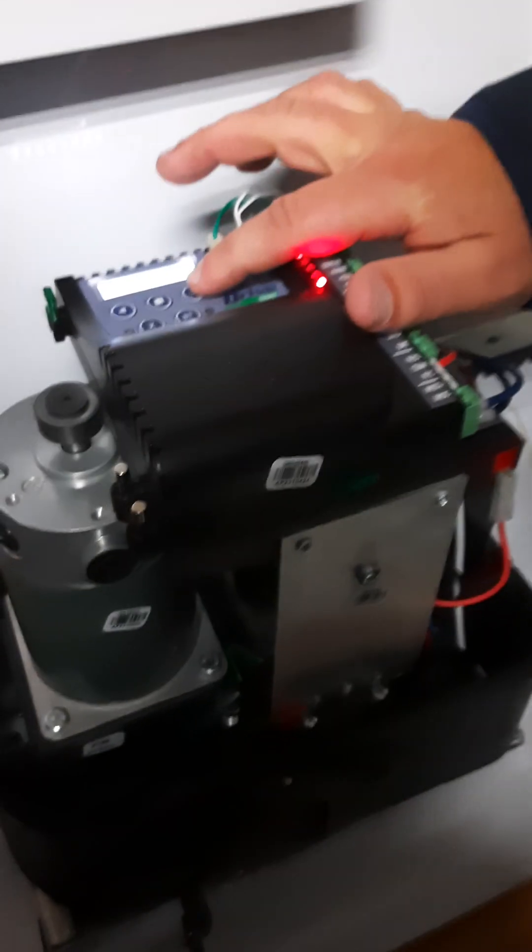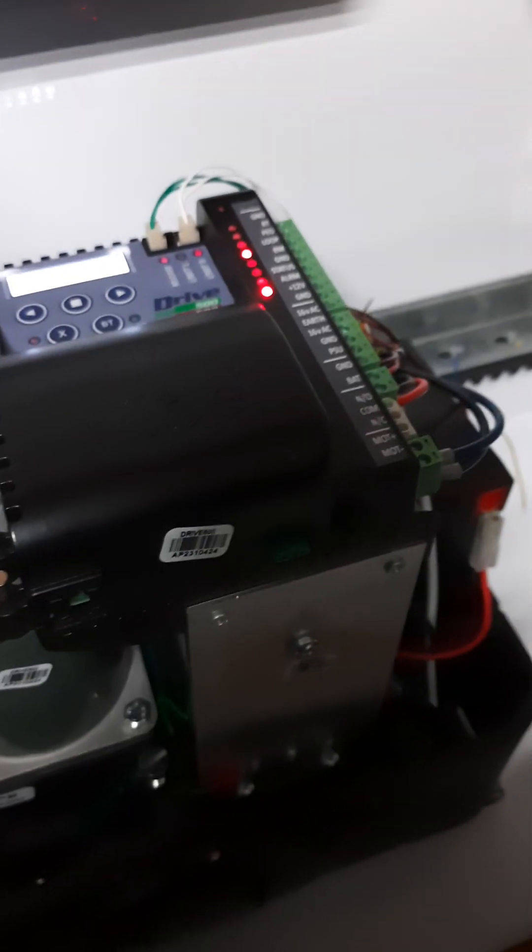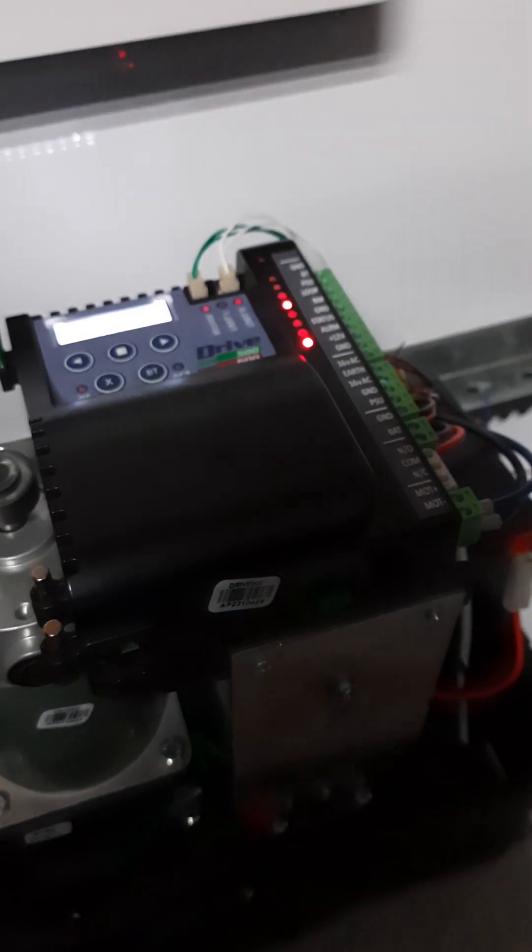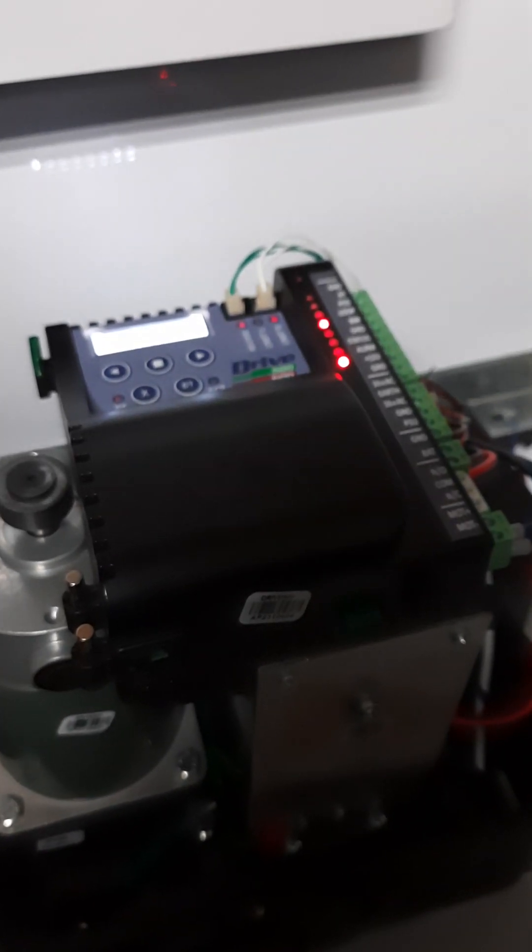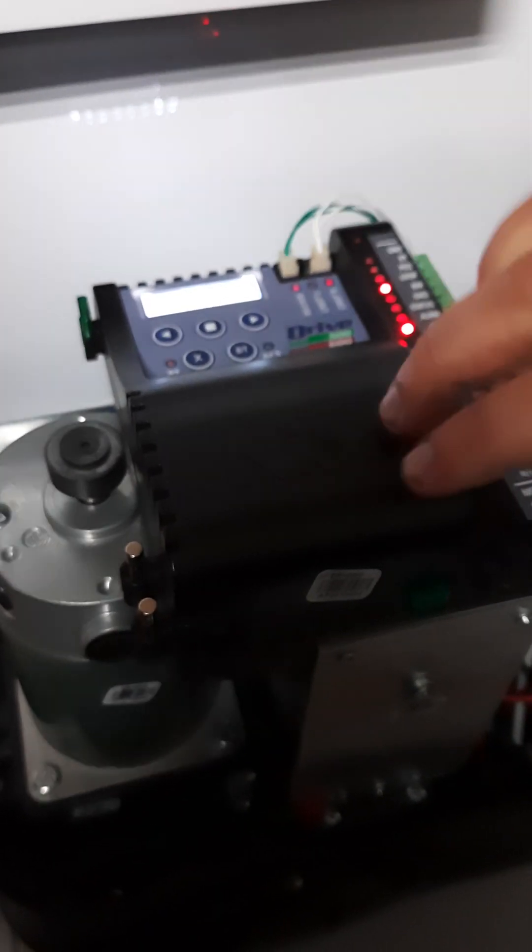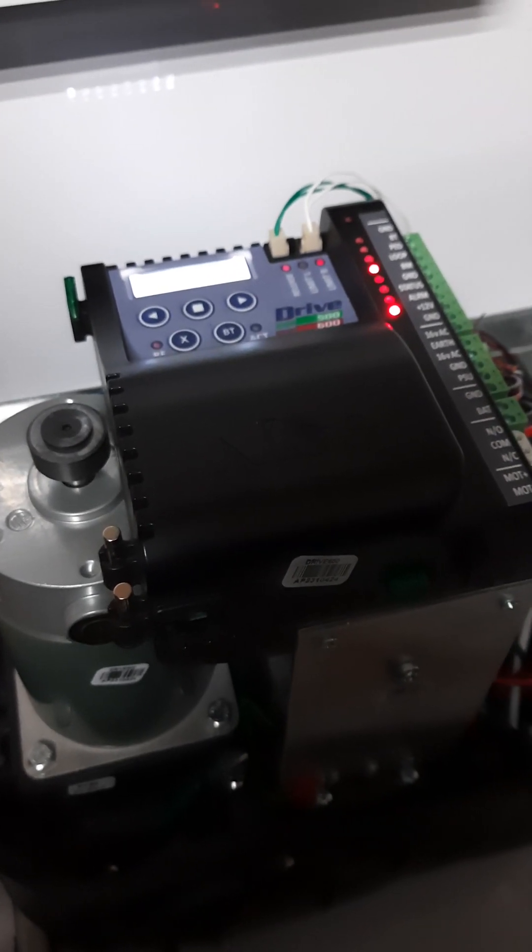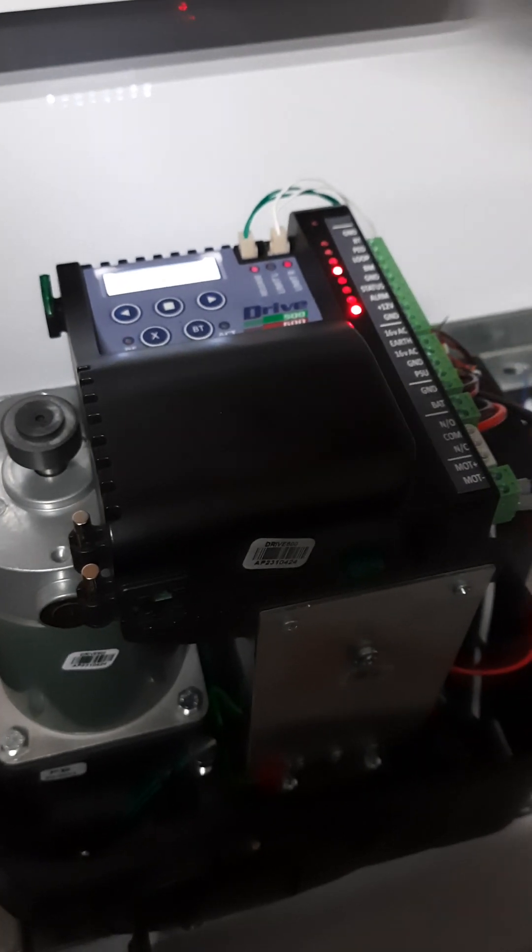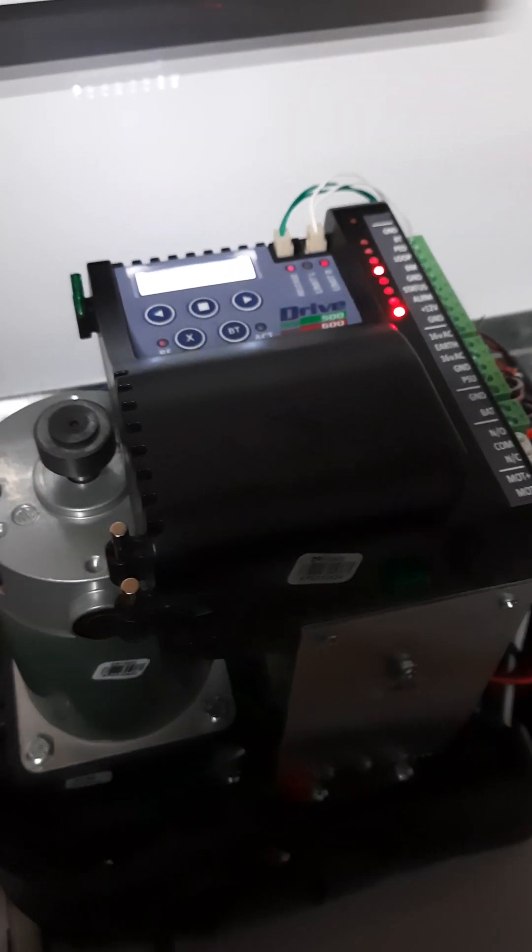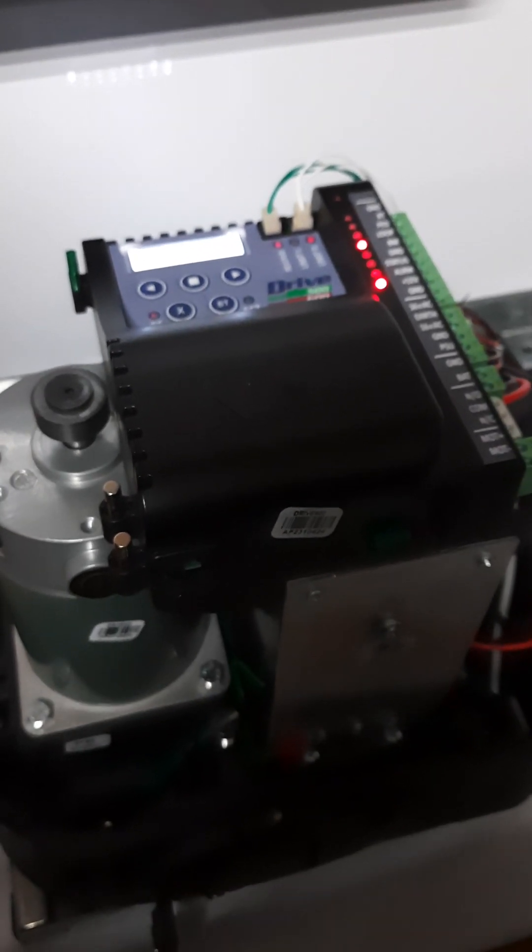And then there's also other functions that you can activate. Back to mode, condo mode. This is used in complexes. So when you have a complex with a single gate, sometimes it can happen that someone is trying to enter and someone is trying to exit. Now you've got them both pressing the remote and now the gate is doing that, it's not opening and closing. So with condo mode active, the gate will only accept a new command once the gate is closed all the way again. So even if I open the gate from this side, it will start to open. If the guy from the other side comes and he presses, nothing is going to happen. The machine will ignore that other remote until it's all the way closed again.